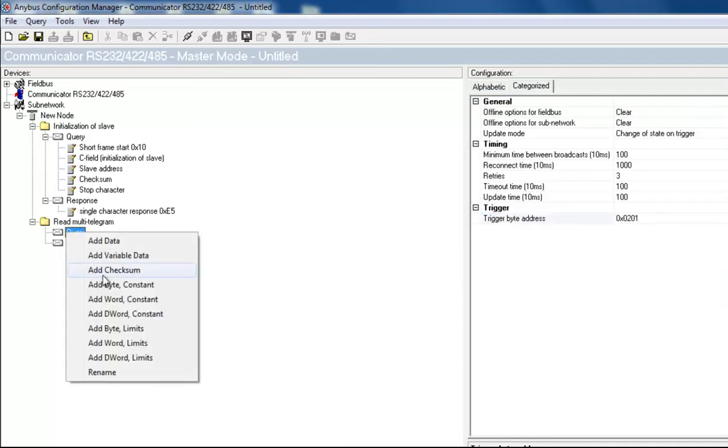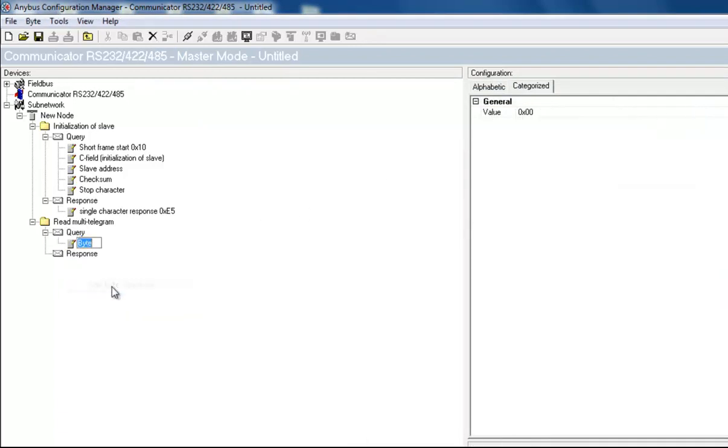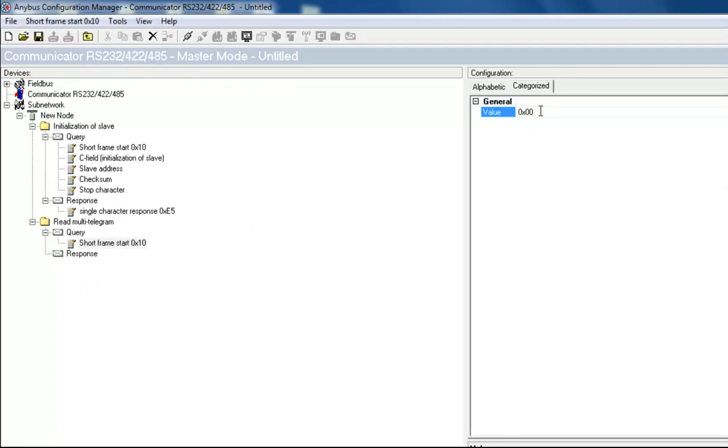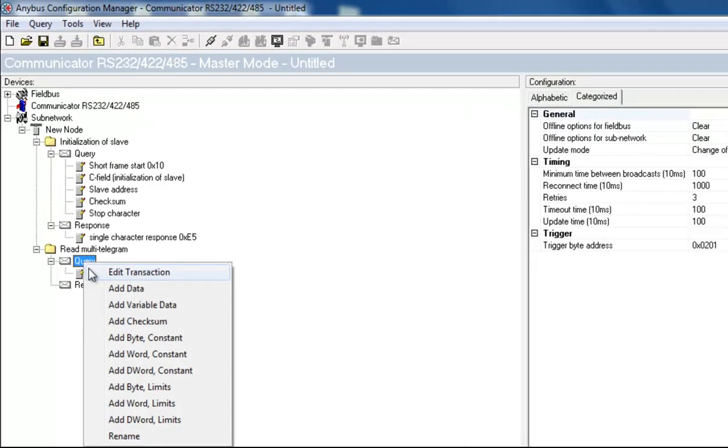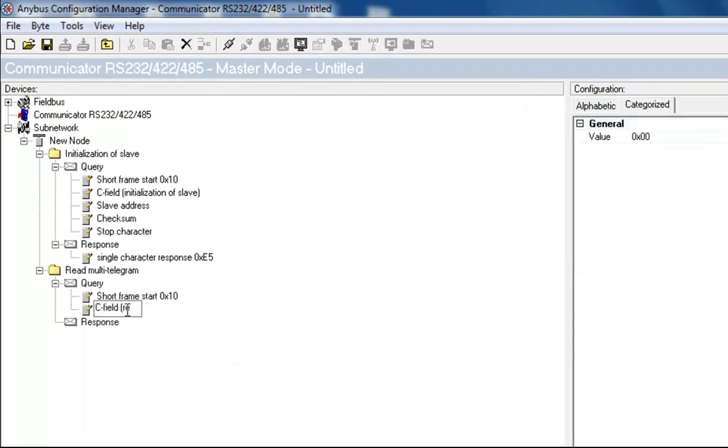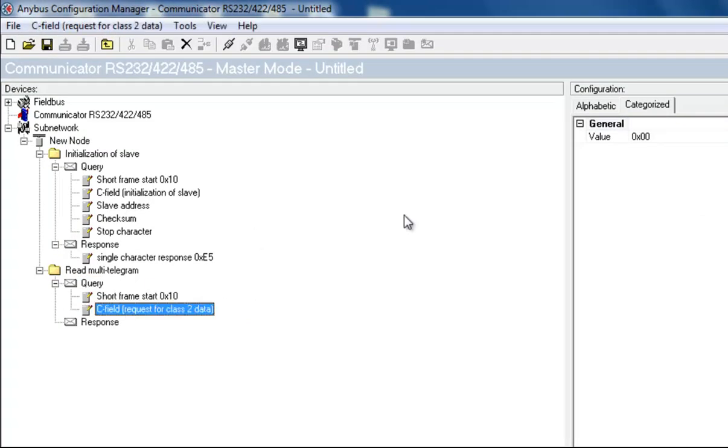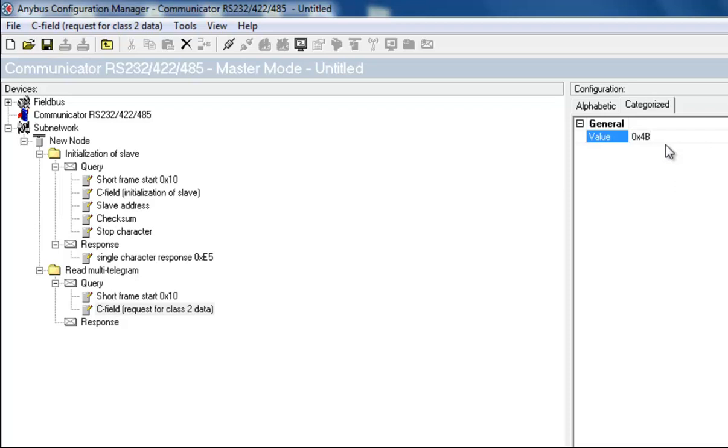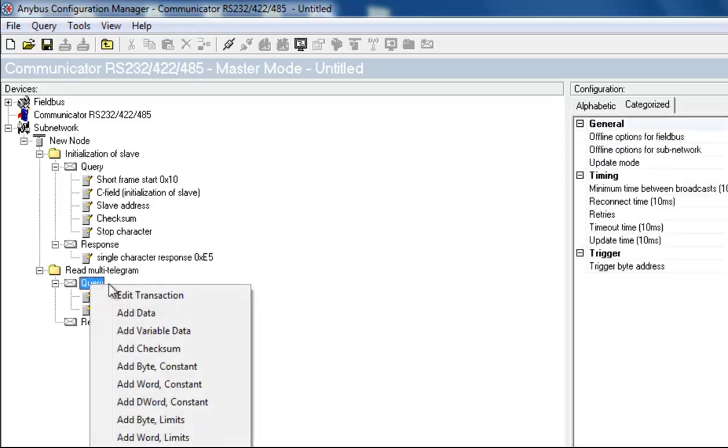Just as I did in the initialization transaction, I now add a short frame start with a value 10, and a C field, which I name request for class 2 data. I set this value to 4b, which means that I tell the energy meter to send all telegrams of class 2.